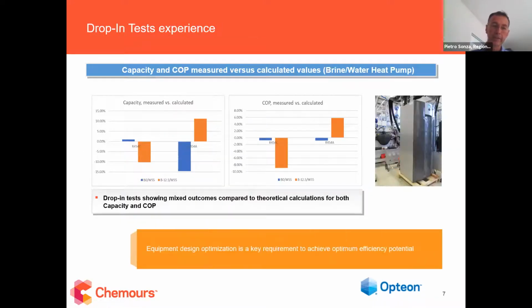Another interesting aspect the industry has been looking at, and that we at Chemours have been very interested in from the beginning, is the capability of dropping in new refrigerants into existing applications. When something new comes on the market, everybody asks: should I design new equipment, or can I use it with my existing equipment? Several drop-in tests have been carried out in different ways, but very often with mixed results. In fact, a simple drop-in in existing systems doesn't lead to satisfactory outcomes, because optimization efforts are required to tune the unit based on the thermodynamic properties of the refrigerant.